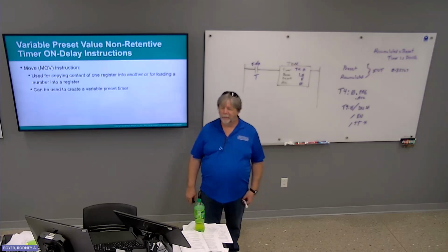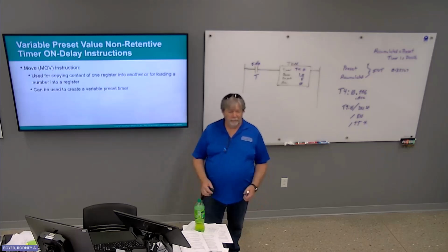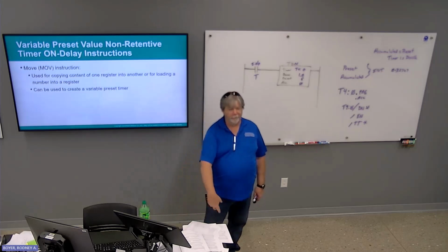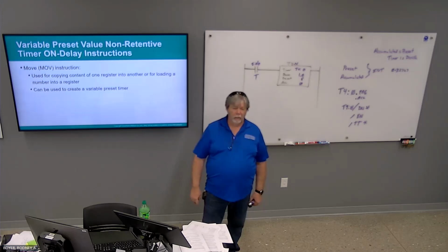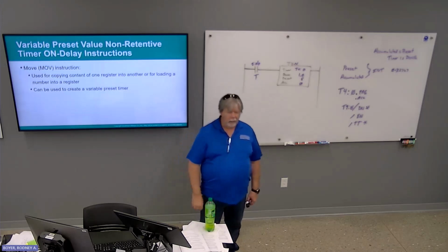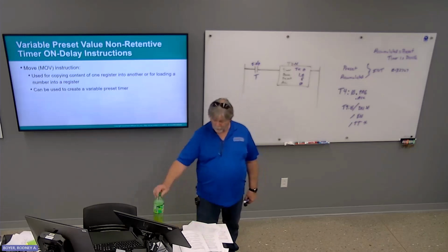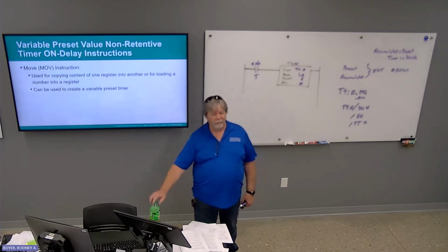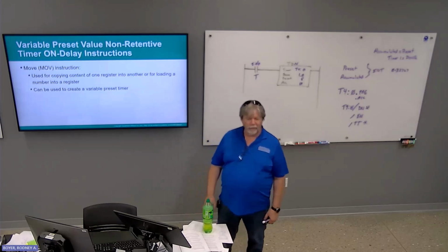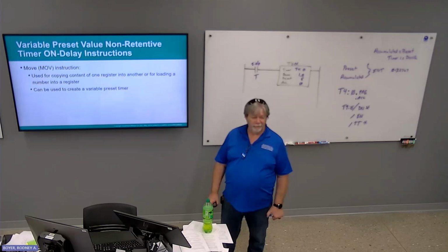Isn't that like the dumbest thing you've ever heard? Or, at least right up there. If I move this from here to there, it's not here no more. It's over there. In the PLC, if you move a value from one register to another, it copies it. So all I have to do is go, oh look, now I've got 2 bottles of soda. Yeah, that is one of those goofy things that if you don't know, it will confuse the heck out of you.